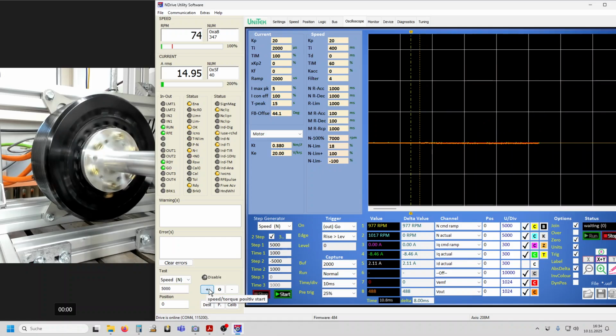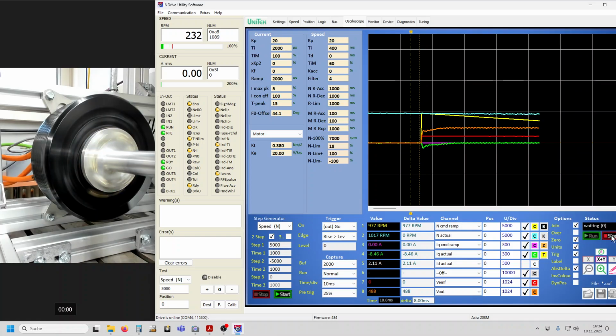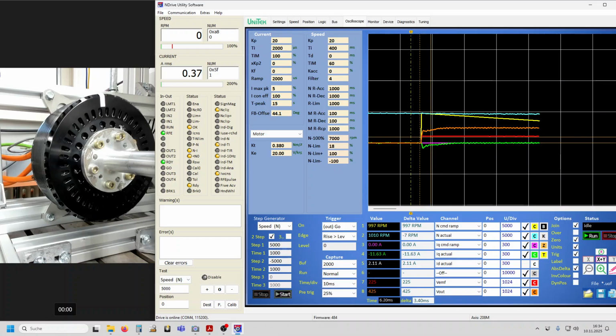Enable the drive, start, disable and enable again immediately afterwards. I'm gonna stop. Now we can see how in red, depending on the factor we have entered, there is a pre-control output. And the AC current spike is a little bit lower because there is already a pre-control. So what is our goal? Our goal is to configure the KE output to have a voltage BackEmf output in red, which will match the total voltage output.